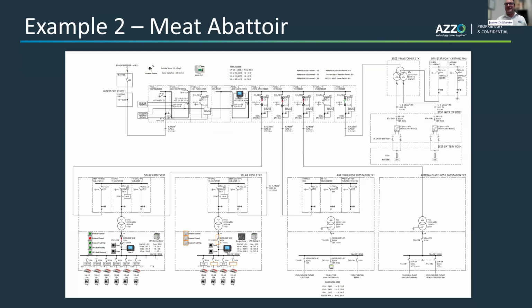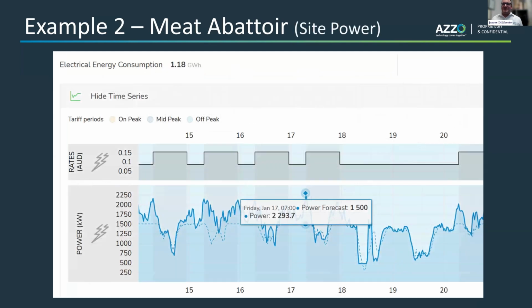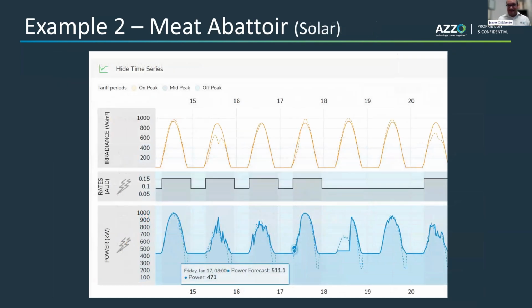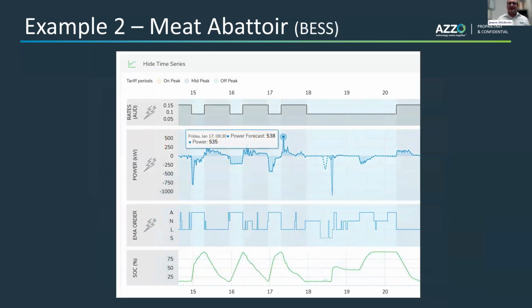On this curve here, you can see a forecast of 1.5 megawatts, but if that jumps up to 2.2 megawatts, what are you going to do instead? You can't rely on your solar, because at this exact time it dipped — a small cloud came over on that day — and that is exactly where the battery kicked in. That little blip on the duration curve, which would be right up towards the front on the left side, was able to deliver the extra capacity that otherwise would have required a larger transformer.